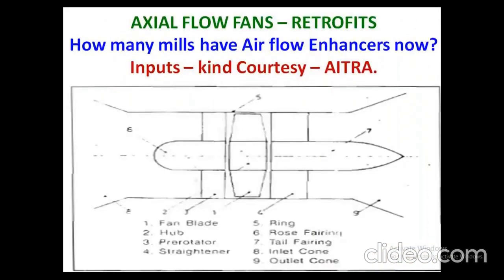Coming to the axial flow fans, this is a big area. ATIRA has given a lot of inputs to the textile mills. If you see, 9 out of 10 mills don't have this tail fairing and nose fairing. The nose fairing and tail fairing is fitted into the existing axial flow fan to streamline the airflow. The airflow is always turbulent. You need a suction bell mouth and a discharge cone type chute to streamline the flow of air instead of turbulence. This itself gives almost 7% savings.